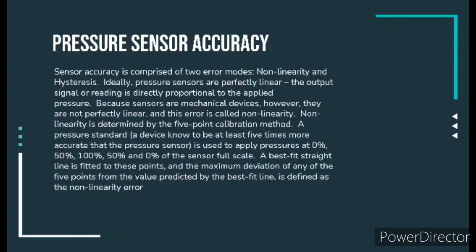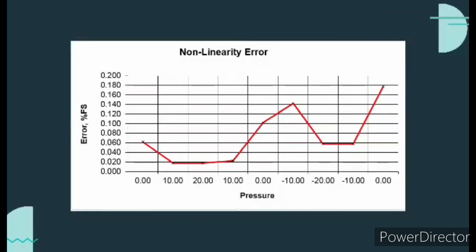A pressure standard, a device known to be at least 5 times more accurate than a pressure sensor, is used to apply pressures at 0%, 50%, 100%, 50%, and 0% of the sensor's full scale. A best fit straight line is fitted to these points, and the maximum deviation of any of the 5 points from the value predicted by the best fit line is defined as the nonlinearity error. This is an example of nonlinearity error.